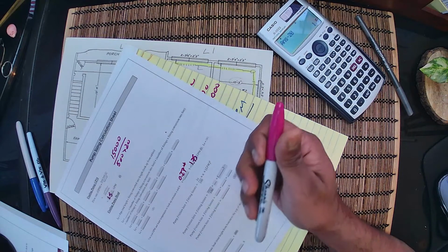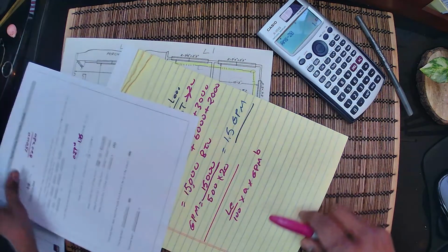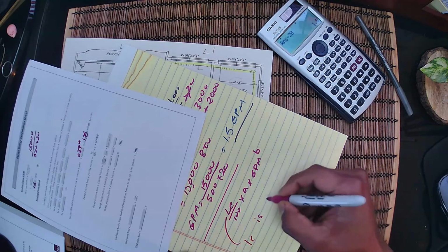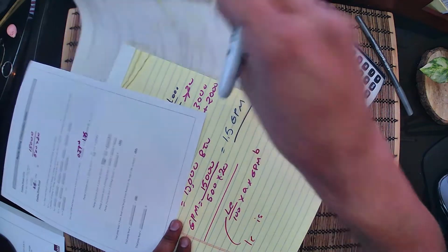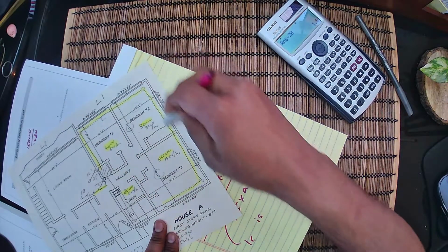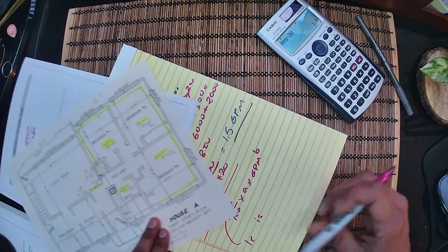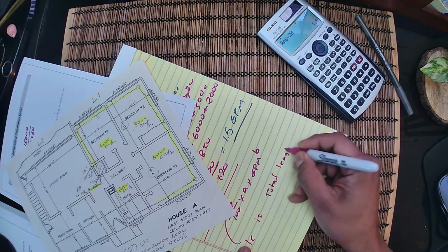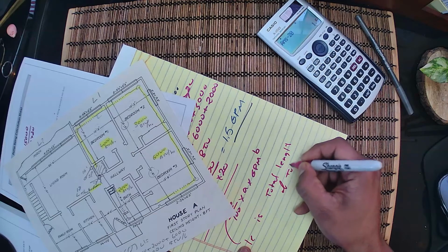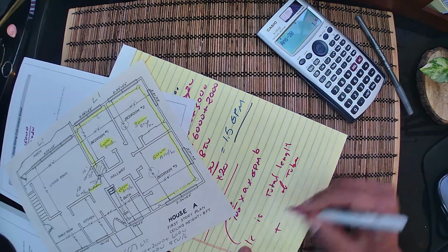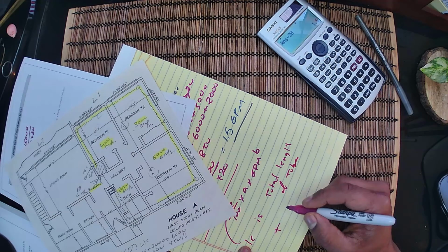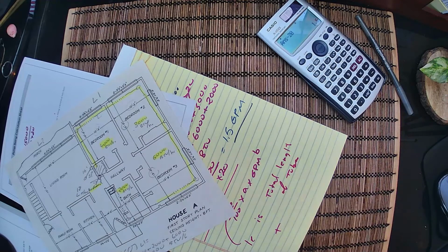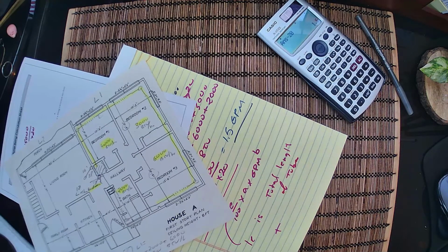What we need now is the equivalent length. What is equivalent length? It's over here. LE is the length of the total pipe you're going to use in your loop, like all the pipe you're going to lay out. And you see this in yellow, I did lay out some pipe. Total length of tube plus the conversion of losses in elbows into length, and that's why it's called the equivalent length.